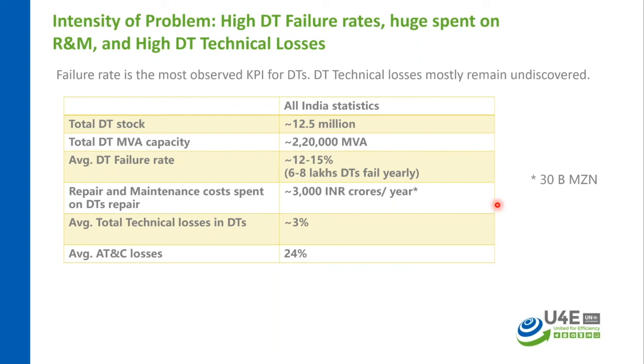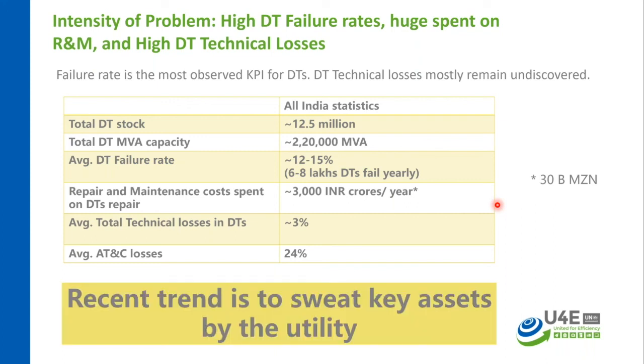The average technical losses on these transformers are around 3%, so energy efficiency is very important. And the AT&C losses in India are 24%, which is higher than Mozambique. I think Mozambique is somewhere around 20%, but still the technical losses will be similar. So the trend is to sweat the existing assets rather than buying new ones.